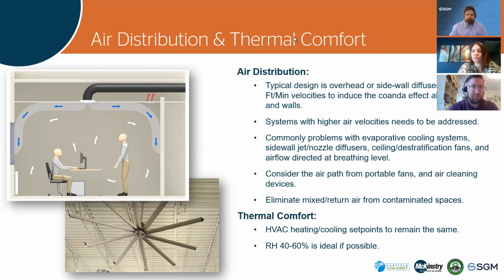Now, some of the common problems we've seen in buildings are evaporative cooling systems, say in large atriums or gyms. These tend to use a lot more air and blow higher velocities. Sometimes there are sidewall diffusers targeting long distances, like 30 feet to the edge of a space, where you'll feel the flow, as well as ceiling and destratification fans. What you're going to want to do with those is either turn them off or reverse the flow so it's pulling air up and not blowing down on people. Additionally, a lot of folks are adding air cleaners at their desks or HEPA in the room.